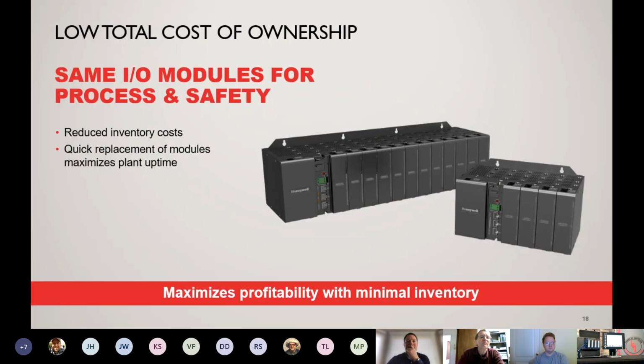As we stated earlier, it uses the same safety I/O and process I/O for both the different applications, so there is less inventory that you have to carry on your shelf. Again, for those applications where you might need SIL 2 safety approval, the HC900 does have that, and it also gives you voting capability inside of the programming of the CPU.